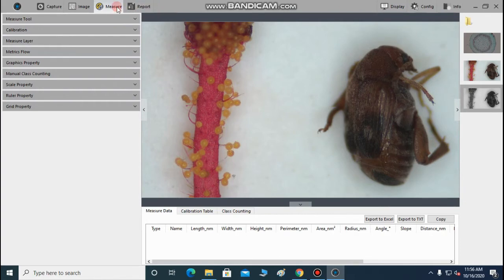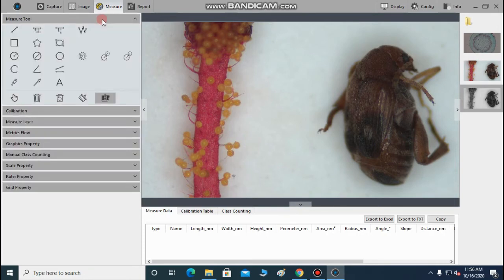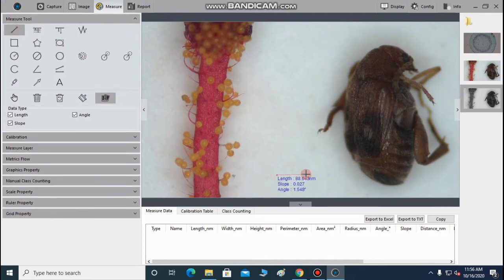This is very important while recording images for research purpose. For example, if you want to know the distance between 2 points in the image, using measurement tools, you can simply draw a line between the 2 points and get real-time measurement data. Pixel level measurement can be converted to more practical units such as millimeter or inches using calibration module in the software.